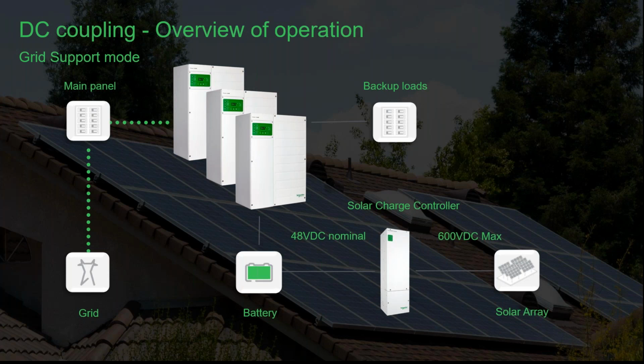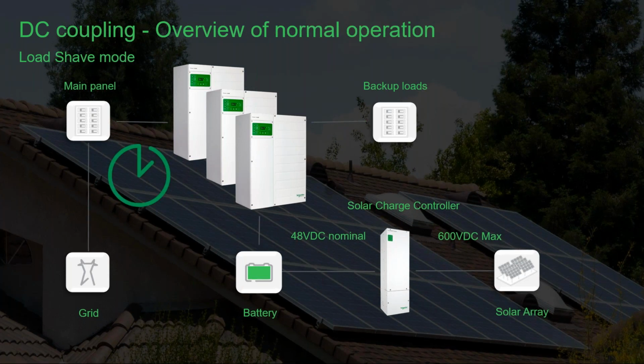When in grid support mode, the PV is used to support the load, typically after the battery is fully charged. When in sell mode, any excess PV will be exported back toward the main panel. Any remaining power will flow back to the grid. Load shave will prioritize stored energy over what is drawn from the grid. Load shave has a start time and a stop time associated with it.